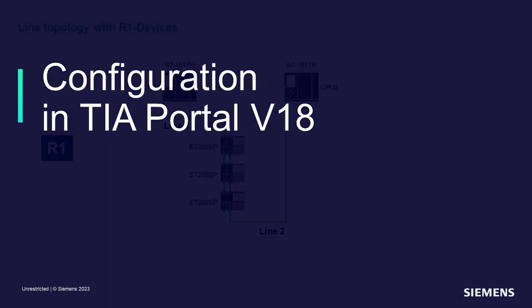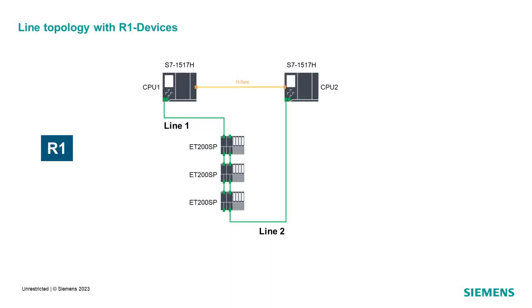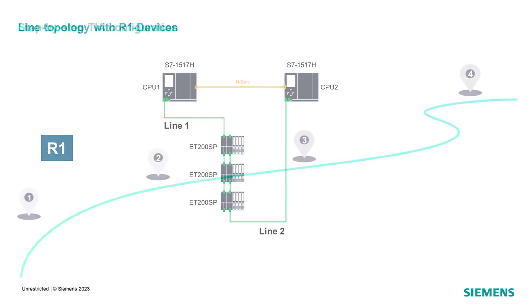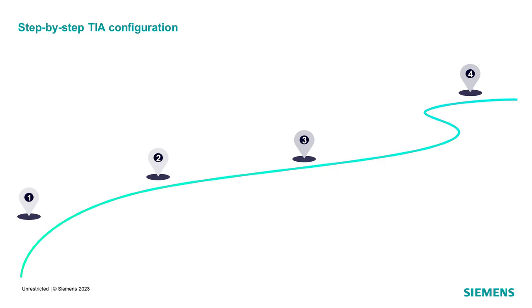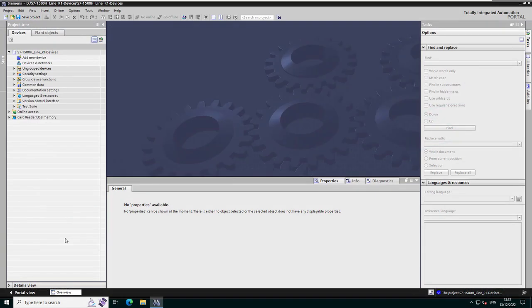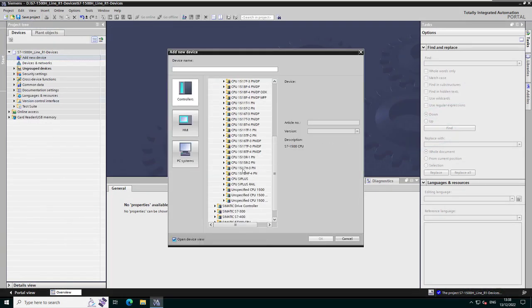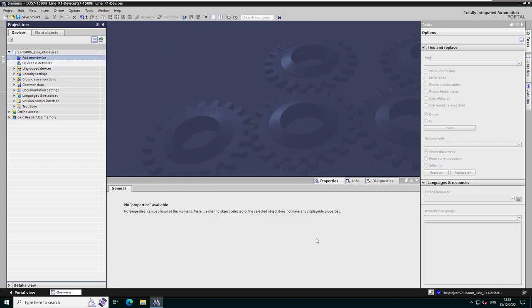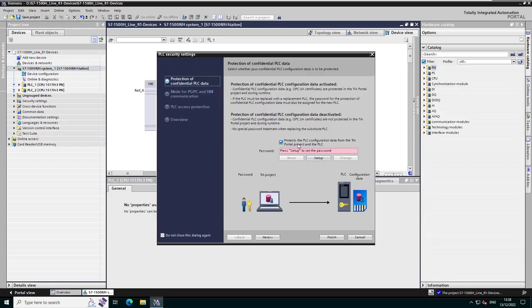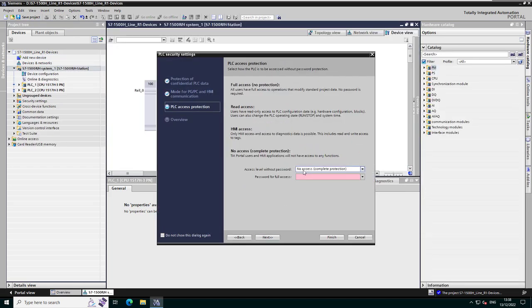Our configuration example is the following: a redundant system based on CPU 1517H and three R1 stations. Such a configuration is done in four steps. Step 1: in your TIA project, add a new redundant controller — here a CPU 1517H — and adapt the security settings required for your application.